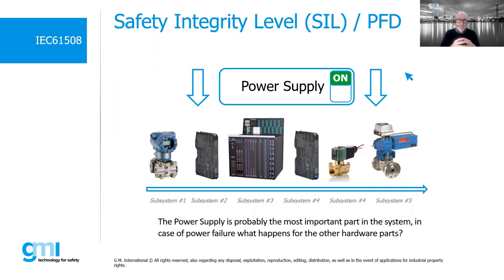All the power supplies that will be part of the SIS, for example, those that will power the PLC and DCS, those that will supply voltage to operate valves and actuators, those that will allow barrier isolators and transmitters to work properly, will also play a fundamental role in a safety related loop. And it's also important that they also have an adequacy level. All components of a SIF, including power supplies, must be safety related and have a SIL level.